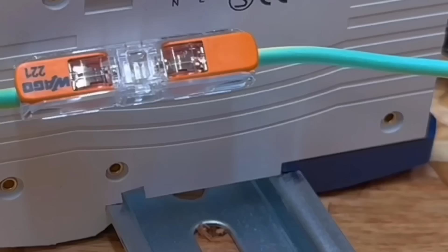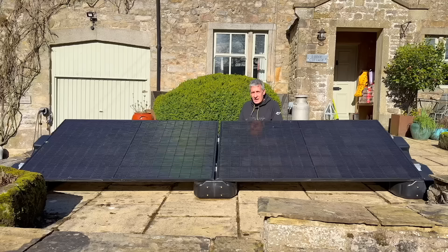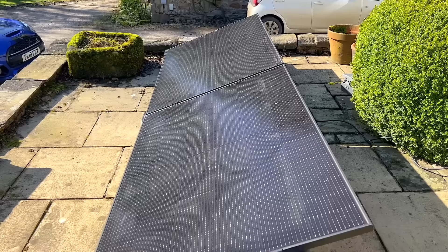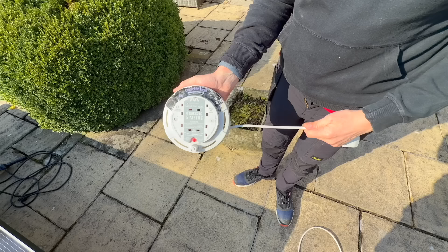Under certain conditions, single-pole RCBOs can be compromised when sources of supply are connected to the load side. This isn't so much of a problem in Germany, as single-pole RCBOs are not common there. He also says there could be problems in households with more than one plug-in solar pack. Normally, they would synchronise with the DNO supply and with each other, and if the power supply is lost, the units should shut down to prevent the circuit becoming an island separate from the grid. But in real life, they could see each other's power and continue operating.